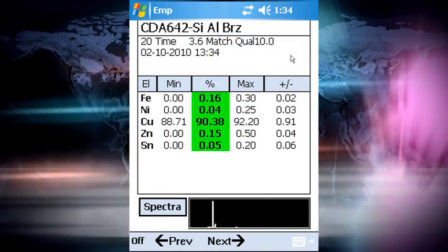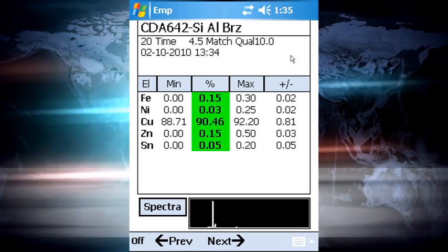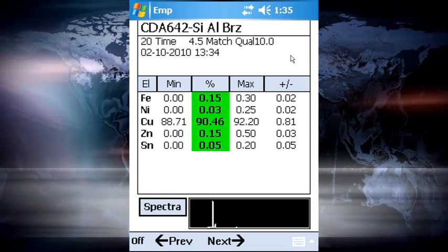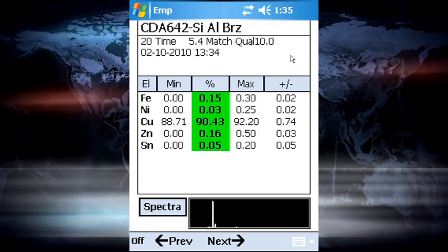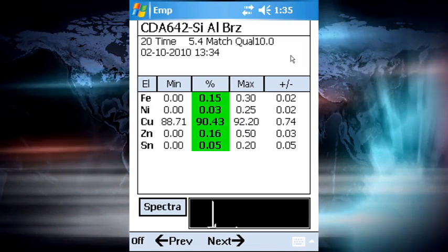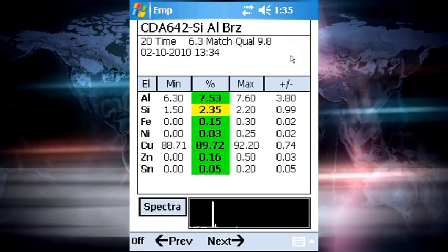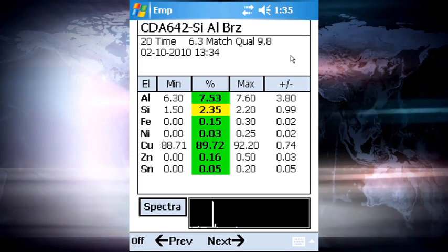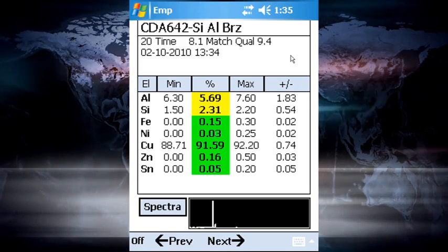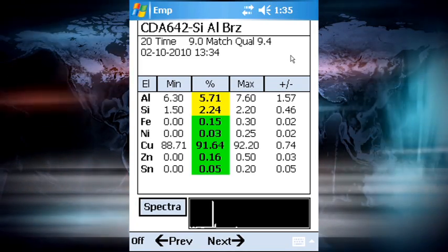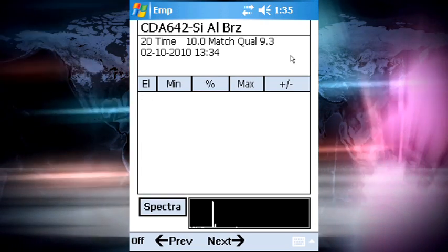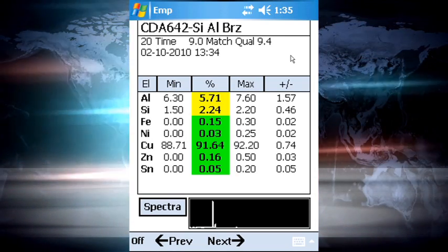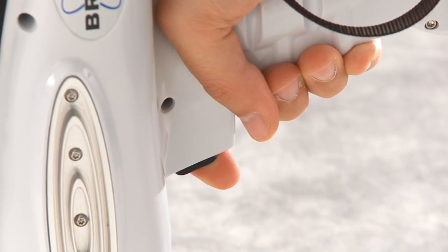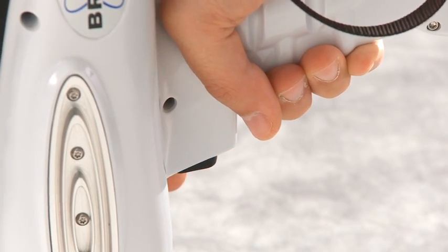The dual mode on the S1 Turbo SD will measure a sample with 2 sets of measurement conditions. The first measurement will be for about 5 seconds, then the voltage, current, and filter will change to allow the measurement of light elements, such as magnesium, aluminum, and silicon. This measurement will run as long as the trigger is activated. If the measurement is terminated before the switch to the second condition, no light elements will be reported.